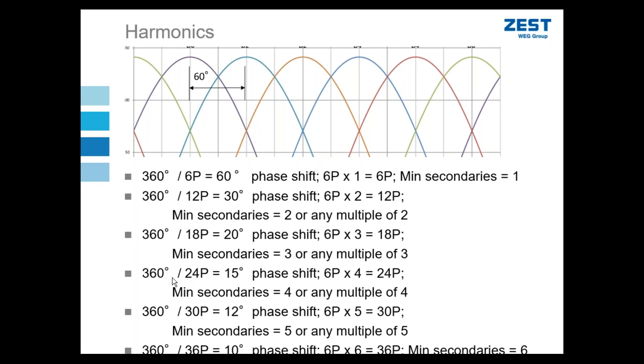Then a 24 pulse system, 360 degrees divided by 24 pulse means I need a 15 degree phase shift, peak to peak. I need at least 4 bridge rectifiers to give me that, that's the minimum requirement for 24 pulse, but I can increase that to any multiple of 4. And so I can carry on and increase to 30 pulse, 36 pulse. We can keep going. We can go right up to 72 pulses, which is practical in some cases.